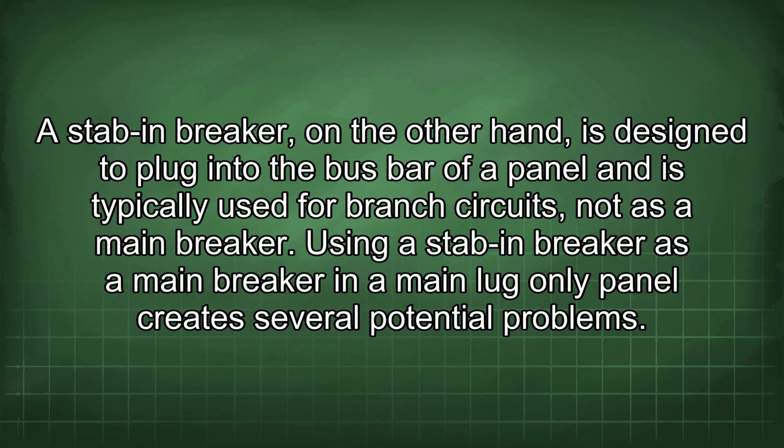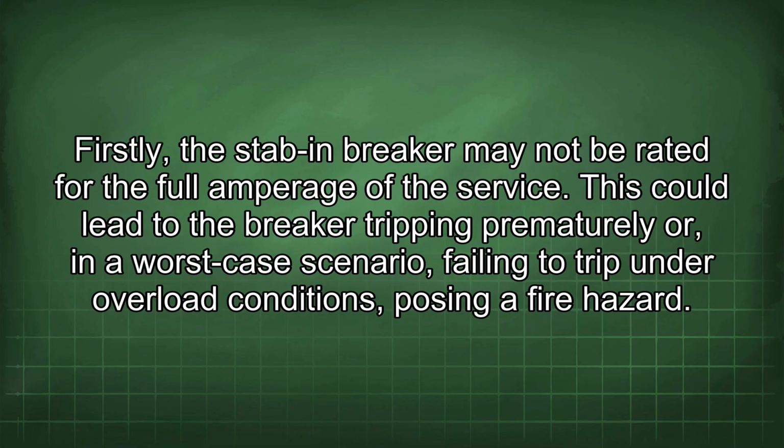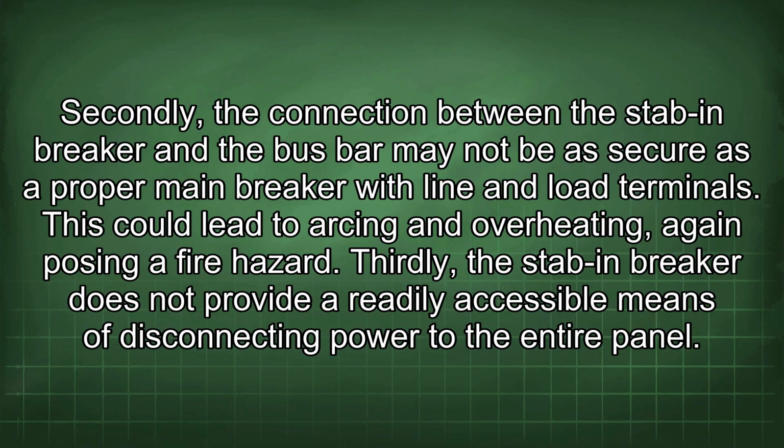Using a stab-in breaker as a main breaker in a main lug-only panel creates several potential problems. Firstly, the stab-in breaker may not be rated for the full amperage of the service. This could lead to the breaker tripping prematurely or, in a worst-case scenario, failing to trip under overload conditions, posing a fire hazard. Secondly, the connection between the stab-in breaker and the bus bar may not be as secure as a proper main breaker with line and load terminals. This could lead to arcing and overheating, again posing a fire hazard.